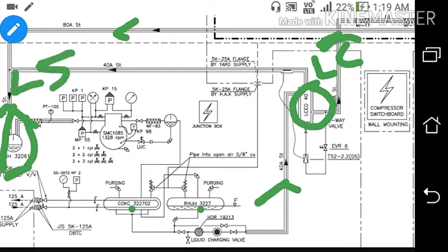First I will be talking about this liquid separator. What is the function of this liquid separator? After the evaporator the refrigerant is almost in a gaseous state, but if some liquid is left in the refrigerant after leaving the air cooler, then the liquid will accumulate in this liquid separator. From the liquid separator the possible excess of refrigerant will gasify, and it will be sucked back to the compressor together with small quantities of oil until the separator has been emptied again.